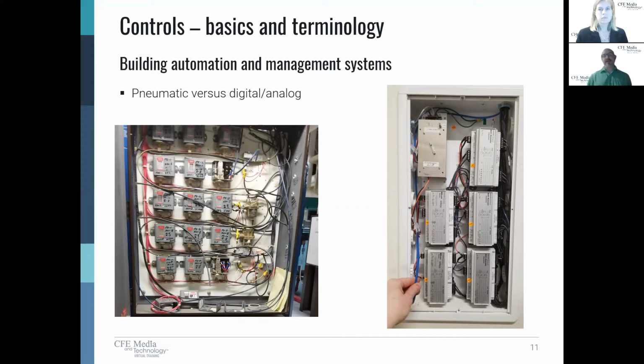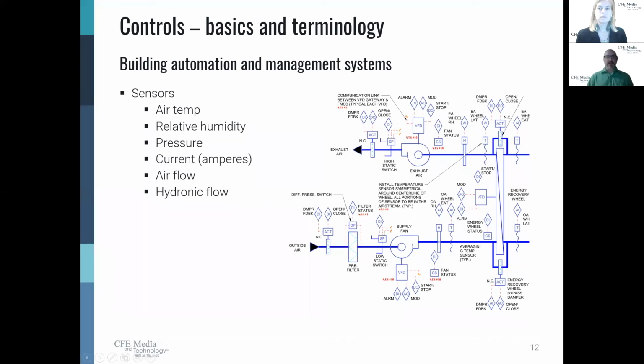But as you'll run into with a lot of remodels, you'll have a mix of old and new. The photo on the right is what we get to. That is an example of a modern digital building automation system cabinet. I can obviously fit a lot more cable, a lot more wires in there, and therefore have a lot more points in a much more compact package. So a building automation system needs inputs, right? Like Johnny 5, it needs input. So we're going to look at sensors, and sensors are going to give us all the variety of parameters that are available to us. Now, they can be hardwired, or they can be communicated over a digital means.